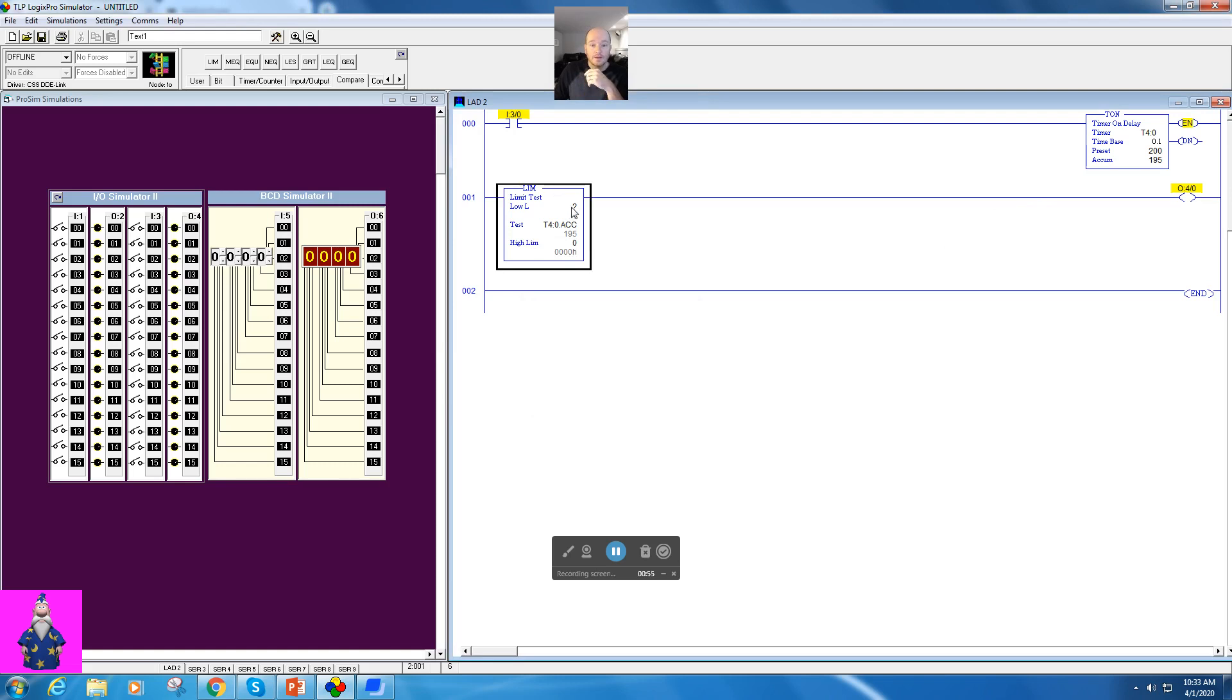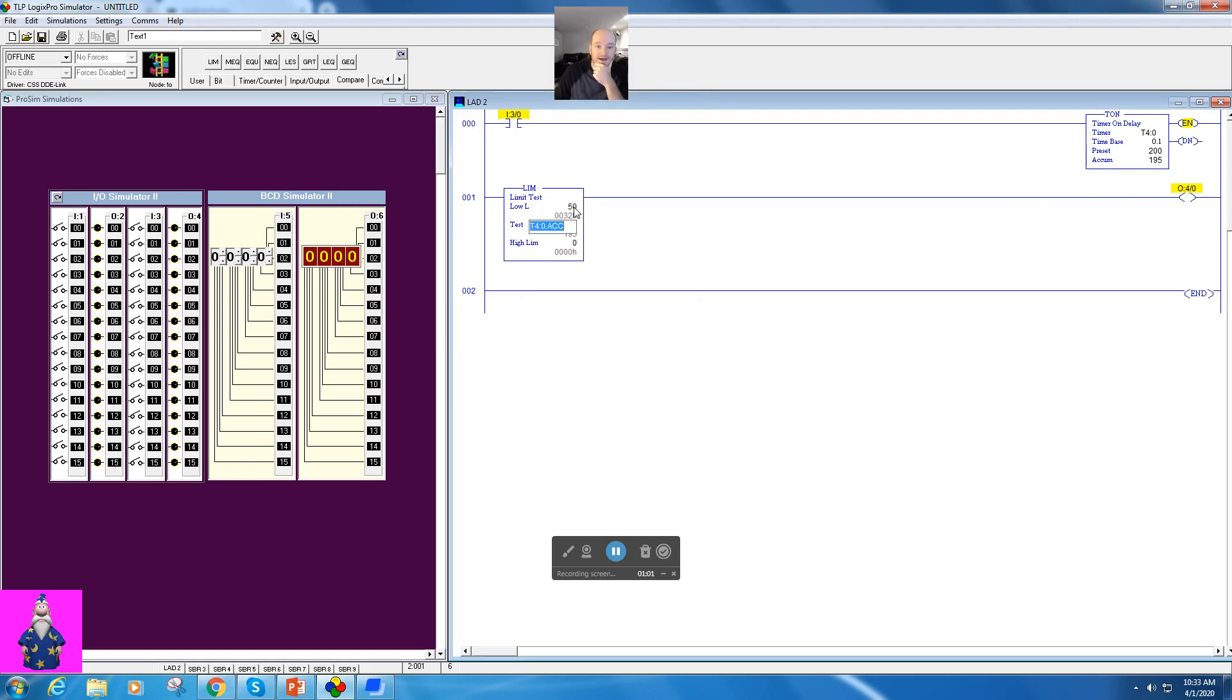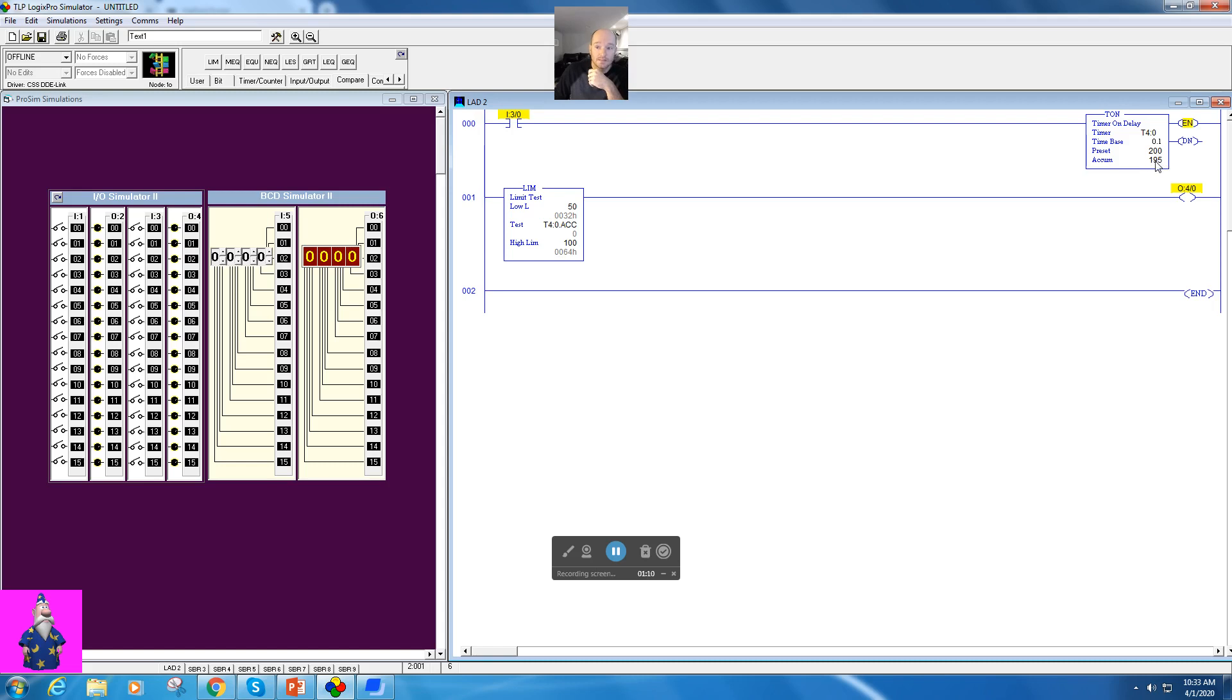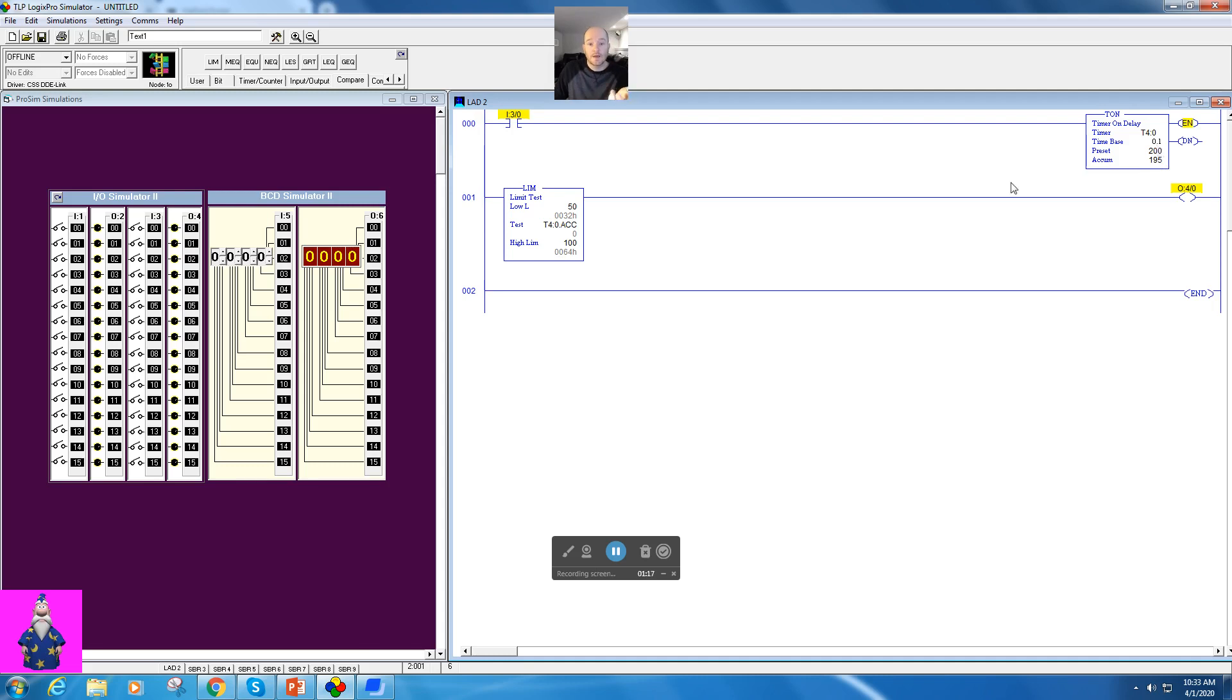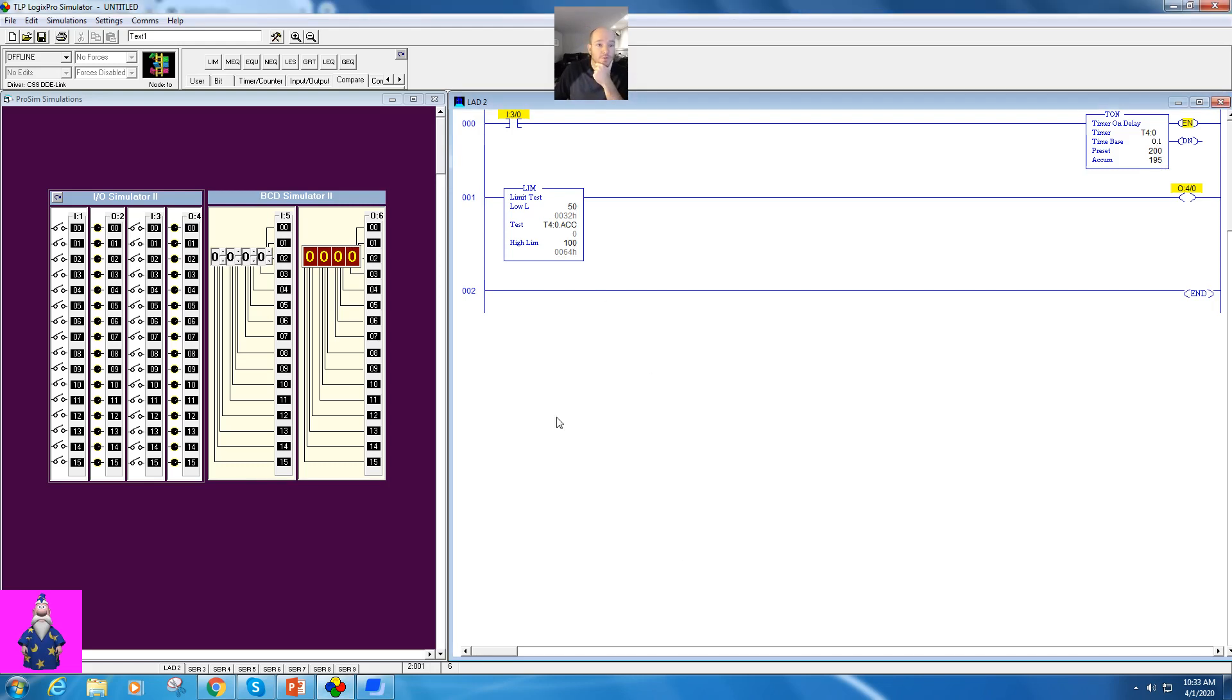Now my low limit, I can have this as a word or just some value. So I'm going to make this turn on between five seconds and ten seconds. Now remember that I have to be able to figure out what I'm doing with this. So if this is 200, but my time base is 0.01, that's a 20 second. So I have to make that same conversion for my low and my high limit. So let me show you how this works.